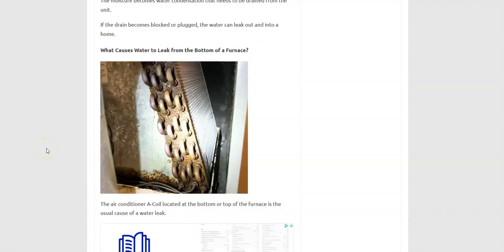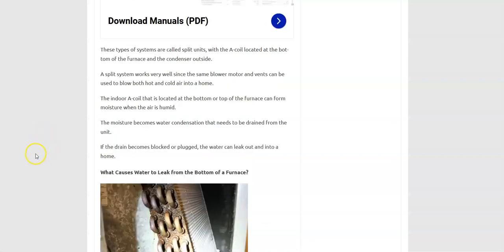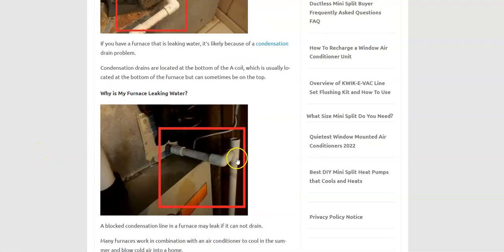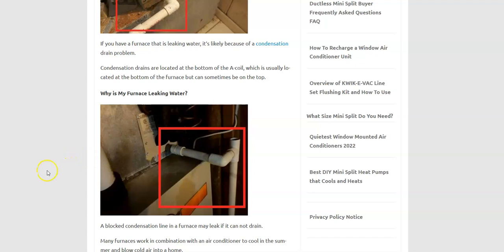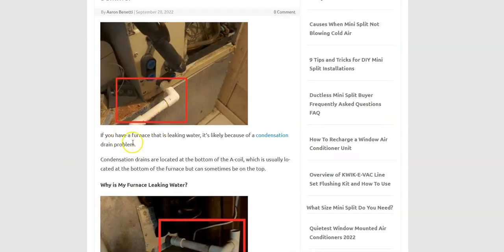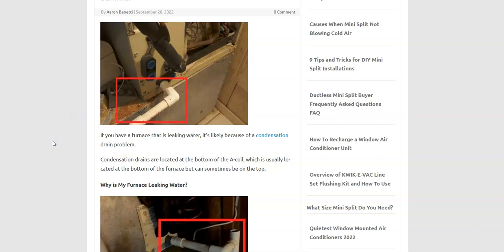If the hole coming out for the drain is plugged up, quite commonly HVAC techs will use a shop vac so that you could suck all this gunk out of the bottom. You could clean this up and then you could suck the gunk out. You can also use a shop vac to help sometimes pull gunk out of the lines. Even though sometimes it doesn't work, sometimes it's too clogged up, you might have to use something like a long piece of wire to reach in and push out any gunk that's possibly in there. In some cases you might just have to go ahead and take apart all the PVC and either clean it up or replace it. It just depends on how bad it's clogged up. If it's not clogged up bad, then you very likely can just push the gunk through, run some water through it and clear it out. But if it's in there bad, then you might have to just go ahead and replace the PVC or the drain line, however they have your system set up.